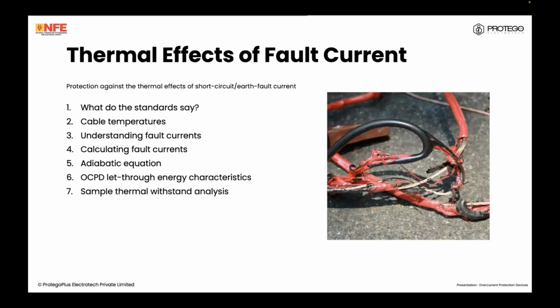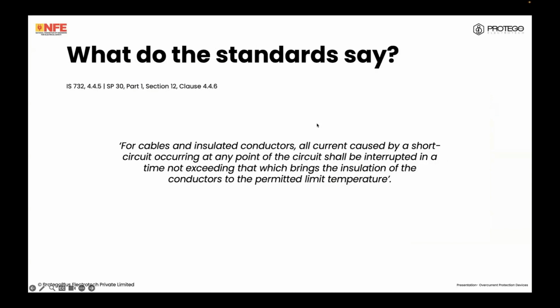Firstly, what does the standard say? Then what are the cable temperatures that are achieved during faults? How is a fault current created? How do we calculate these fault currents? How does this tie into the adiabatic equation? And what this has to do with the OCPD let-through energy characteristics that I showed you earlier. And we'll do a sample thermal withstand analysis. This is a cable that has been badly damaged, by the way.